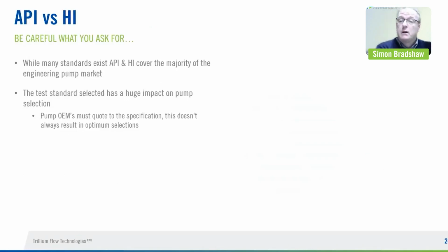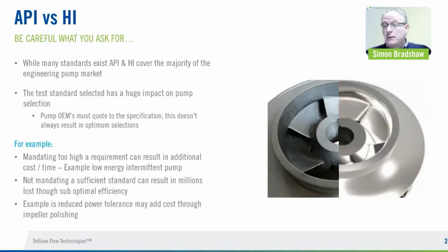Okay. So, careful what you ask for. We talked about there's a number of test standards: API 610, HI 14.6, ISO 9906, and there are some others that we didn't mention here. The standard has a huge impact on the pump selection. It's really important that you get the pump OEMs quoting to a consistent set of testing and test tolerances, so that you're able to compare the offerings consistently.